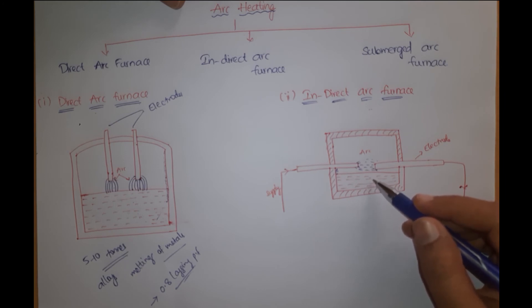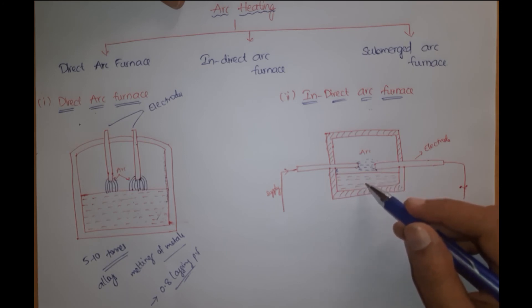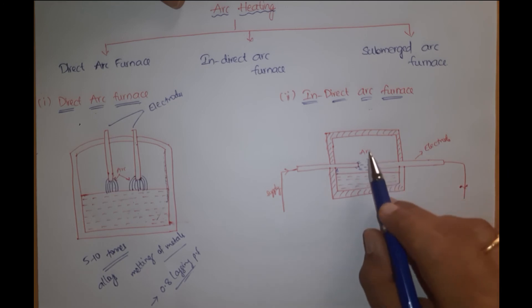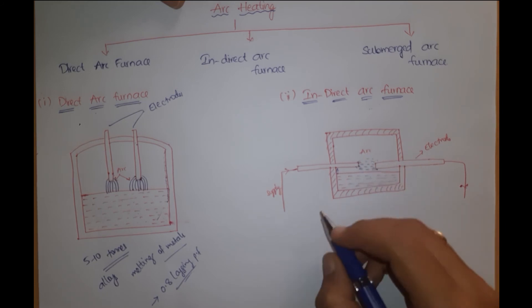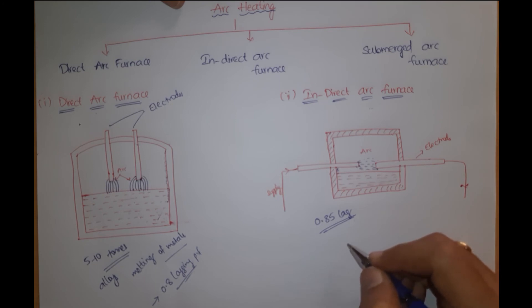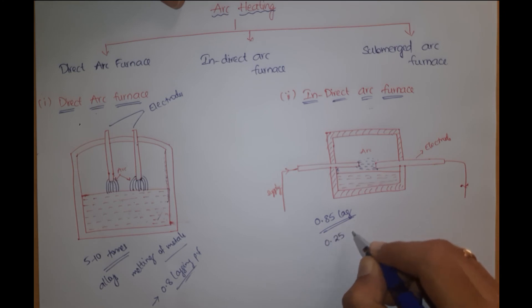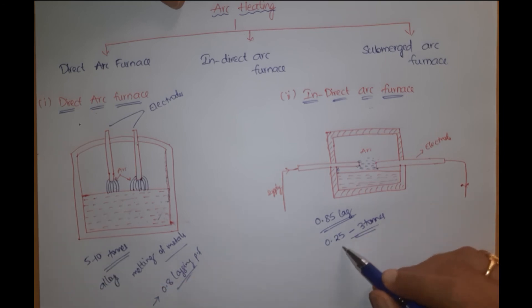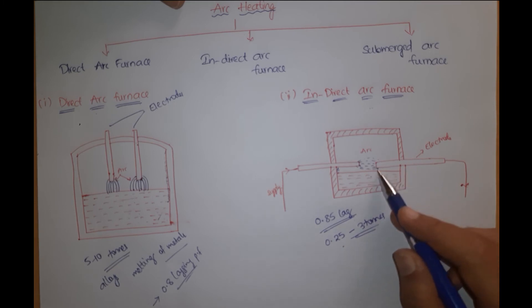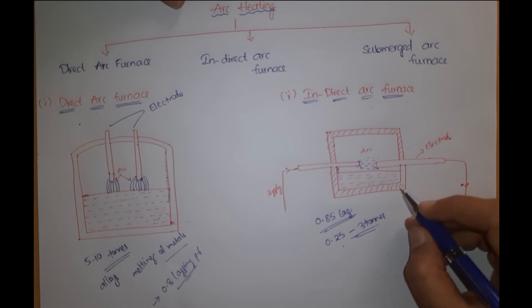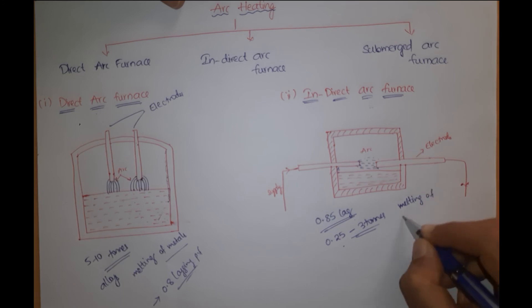Single-phase AC supply is used for this indirect arc furnace. The power input can be regulated by adjusting the length of the arc by moving the electrodes. Coming to the power factor, it operates at nearly 0.85 lagging power factor, and the capacity of the furnace is about 0.25 to 3 tons — lesser than the direct arc furnace because its efficiency is lower due to heat transfer through radiation. These furnaces are mainly applicable for melting of non-ferrous materials.